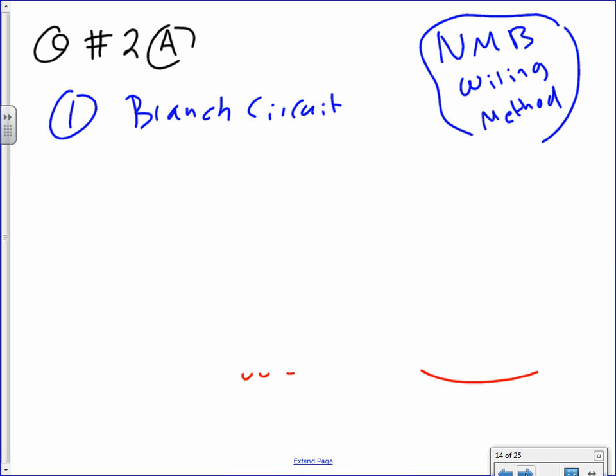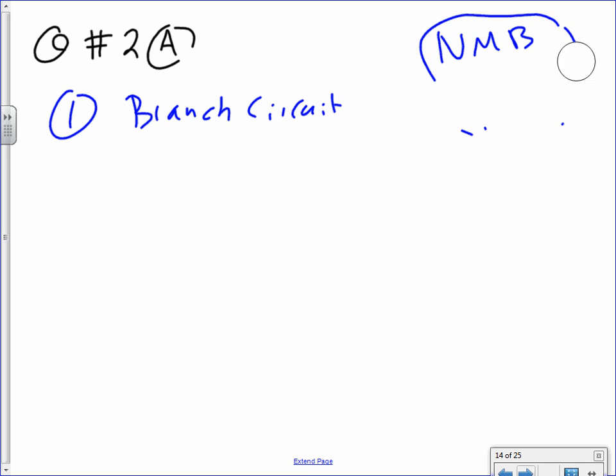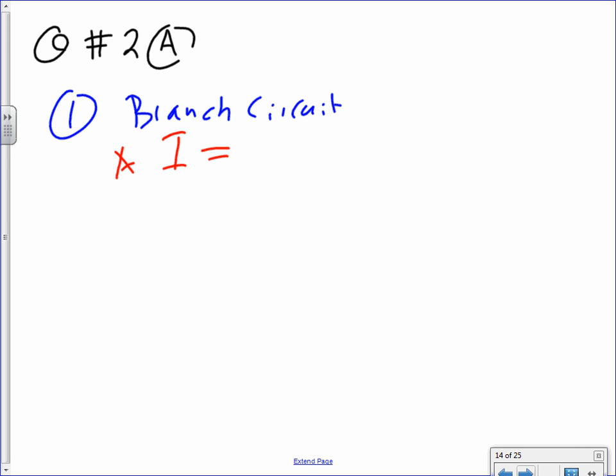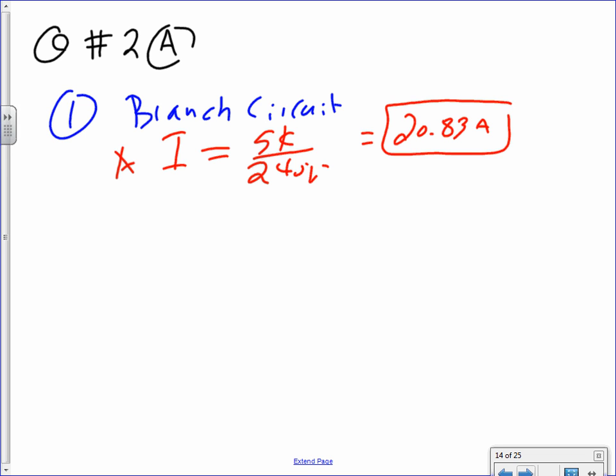Okay. All right, so let's go ahead and size the branch circuit. We reminded you guys that the wiring method is NM-B. I need to do the branch circuits. The first thing you need to do is find the current. I equals, for load A, 5K divided by 240 volts, and that will get you a healthy 20.83 amps. That's the amps of this equipment. It's a continuous load, so 1.25 multiplied by 20.83 gets you 26 amps.